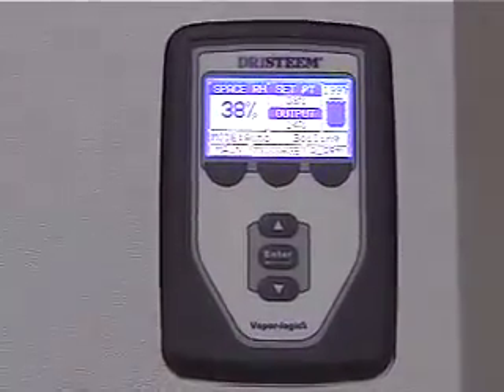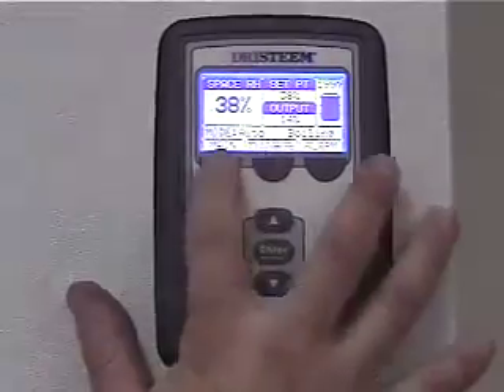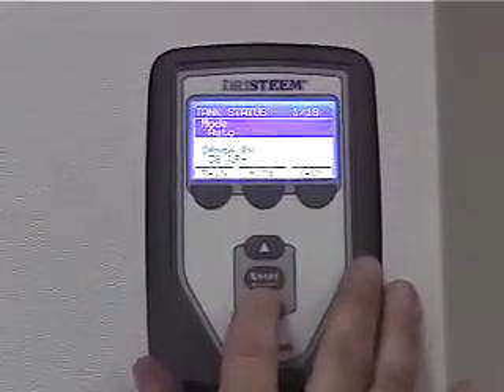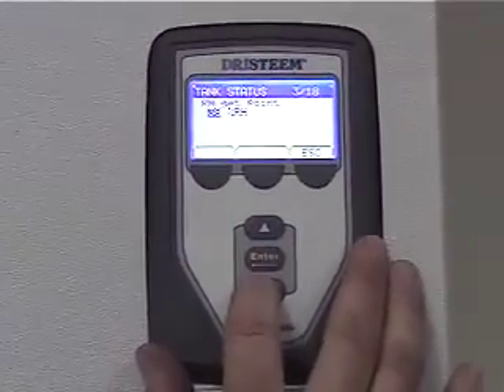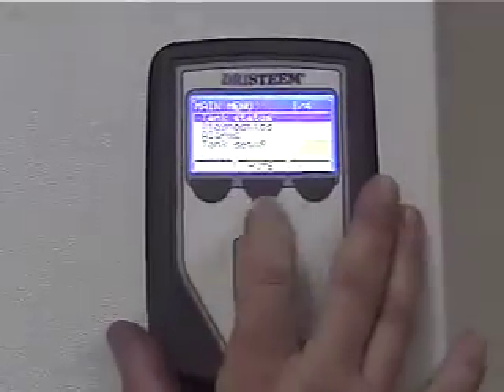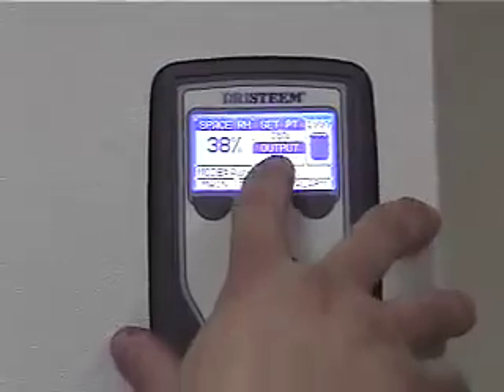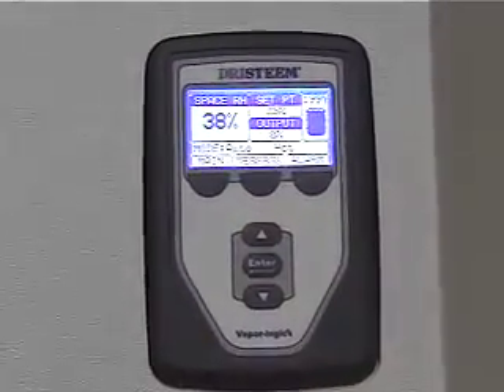Now the reason we're staying there, our set point's at 38%. He was at 35. Oh, 35. Yeah. Trying to figure out why this will stay on. Now if you come back to the main screen, it'll actually tell you. You'll see your output change to 0. How long did the fan stay on after? I think it's got about a 1 minute time delay. Yep. We'll know in just a minute.